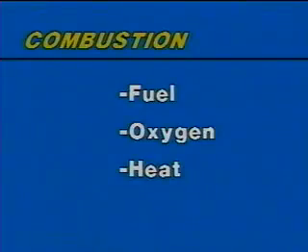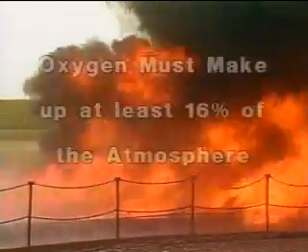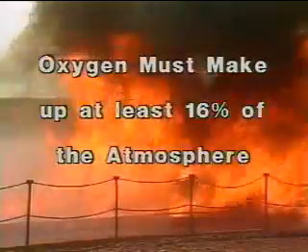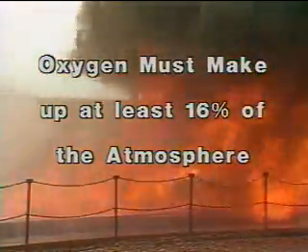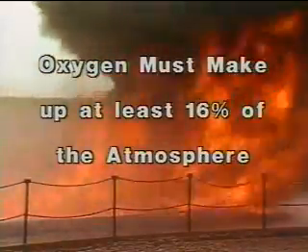However, simply combining fuel, oxygen, and heat will not necessarily produce combustion. First, oxygen must make up at least 16% of the atmosphere for fire to burn. In some cases, 12% oxygen may be sufficient for a smoldering fire.